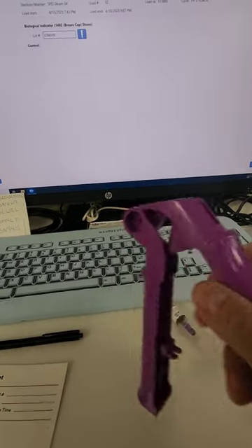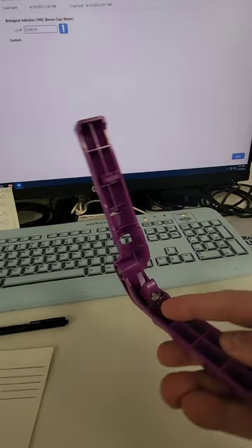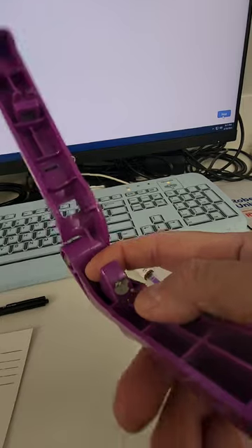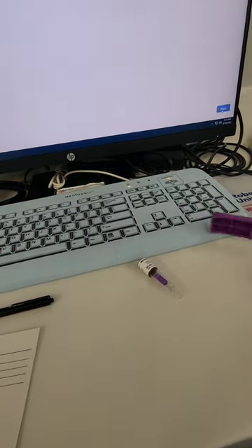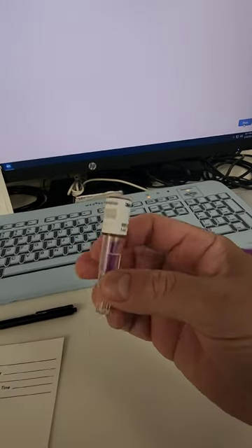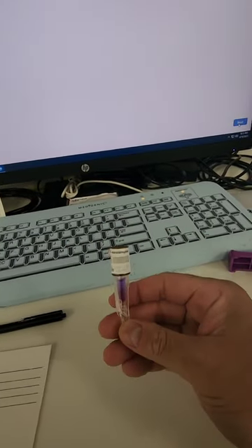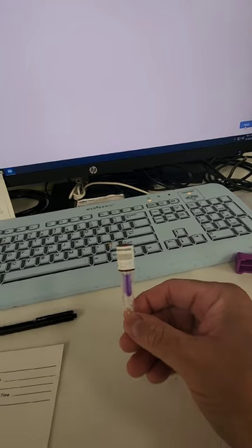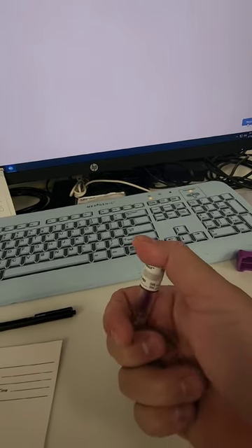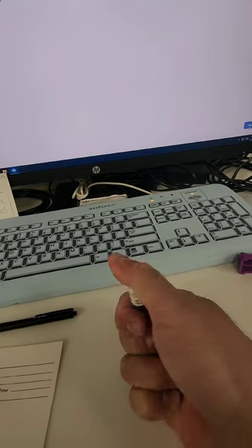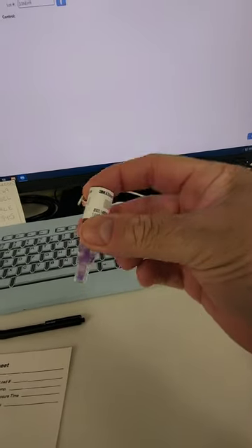biological. Now, the crusher is what you should be using to activate your biological, but I kind of dislike the design of that because it always rips off the type 1 indicator on the top. So when these came out initially, there was 3 ways to activate them, and I've always stuck with this method. It's just squeeze it down, it'll crack.